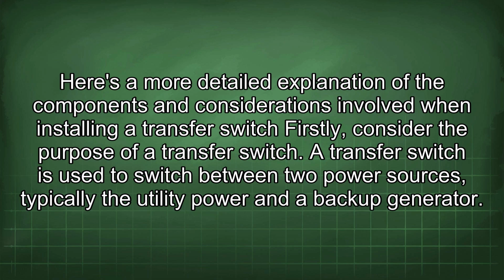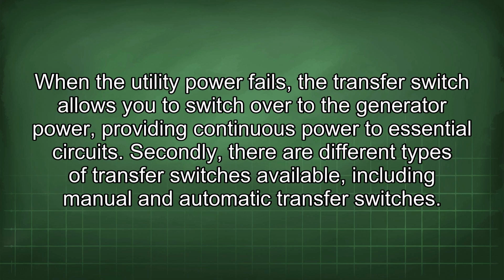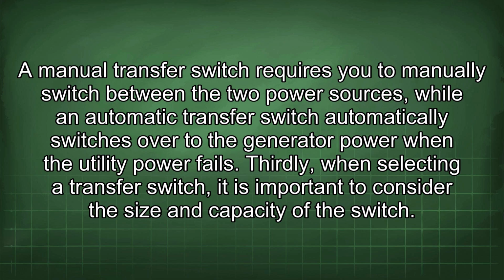Here is a more detailed explanation of the components and considerations involved when installing a transfer switch. Firstly, consider the purpose of a transfer switch. A transfer switch is used to switch between two power sources, typically the utility power and a backup generator. When the utility power fails, the transfer switch allows you to switch over to the generator power, providing continuous power to essential circuits. Secondly, there are different types of transfer switches available, including manual and automatic transfer switches. A manual transfer switch requires you to manually switch between the two power sources, while an automatic transfer switch automatically switches over to the generator power when the utility power fails.